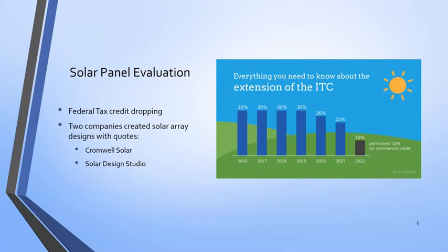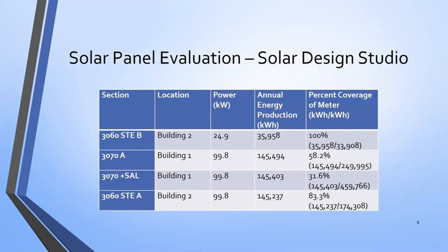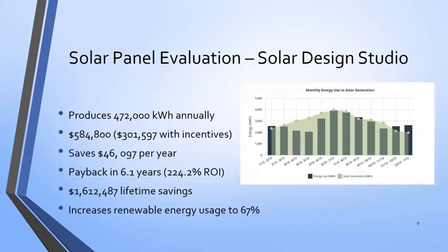I talked to two different companies: Cromwell Solar and Solar Design Studio. Cromwell Solar was able to present a single array of 99.9 kilowatts. After the incentives and depreciation, it came out to about $90,000. But this one array would save almost $12,000 a year in electricity costs, with about a seven-year payback and over $400,000 as a lifetime return. Solar Design Studio took a more aggressive approach and designed four different arrays spanning in size, with three of them being 99.8 kilowatts — roughly the maximum you can have on a single meter — because there were four different meters at the facility. With all that production, it produces over 470,000 kilowatt hours annually, and after incentives costs about $300,000, saving over $45,000-$46,000 annually to pay back in about six years.